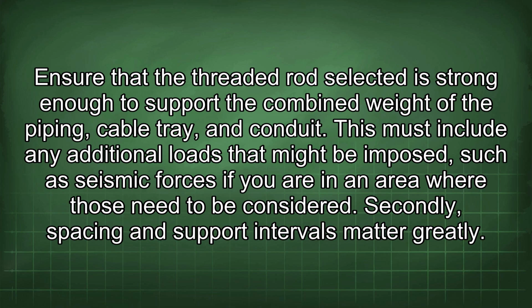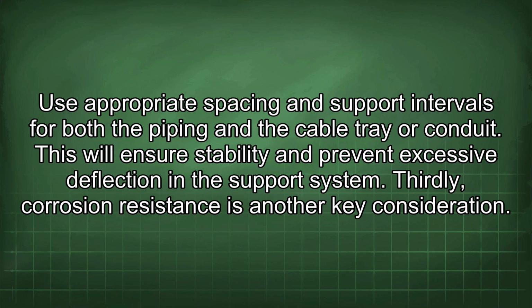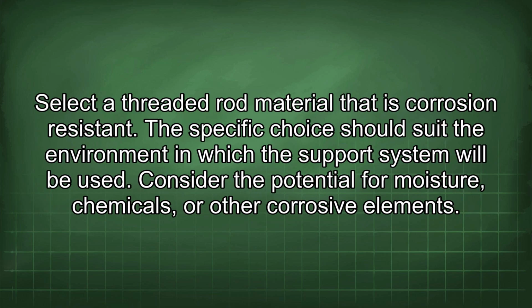Secondly, spacing and support intervals matter greatly. Use appropriate spacing and support intervals for both the piping and the cable tray or conduit. This will ensure stability and prevent excessive deflection in the support system. Thirdly, corrosion resistance is another key consideration. Select a threaded rod material that is corrosion resistant. The specific choice should suit the environment in which the support system will be used. Consider the potential for moisture, chemicals, or other corrosive elements.